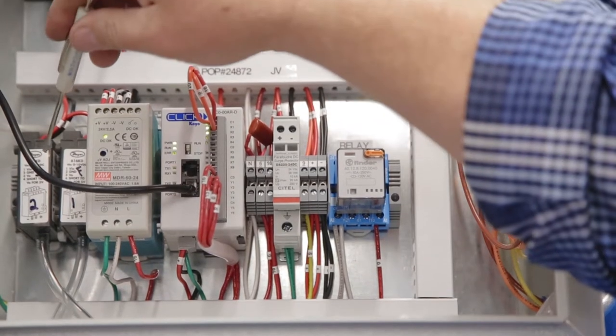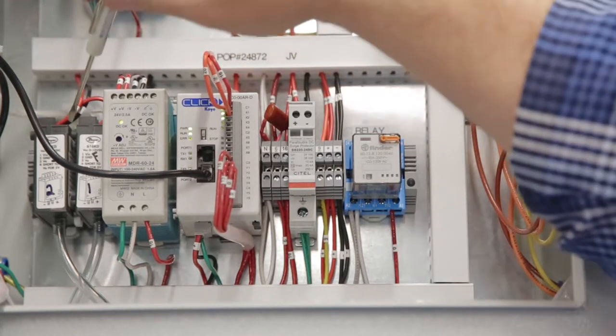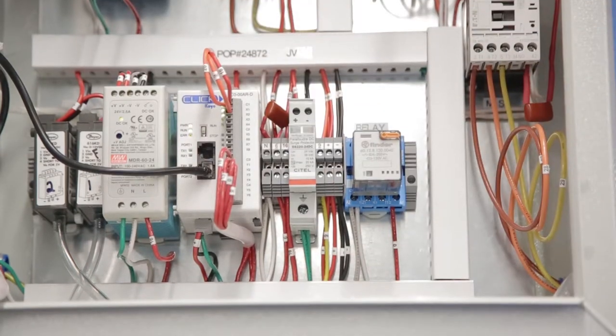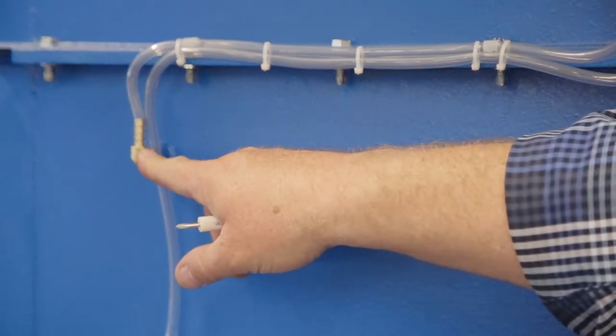These are the pressure transducers. Sometimes you'll see them labeled as F, S, and D if this were a ducted unit. F would be the highest pressure. There's a pressure connection above the impingers, below the blower.